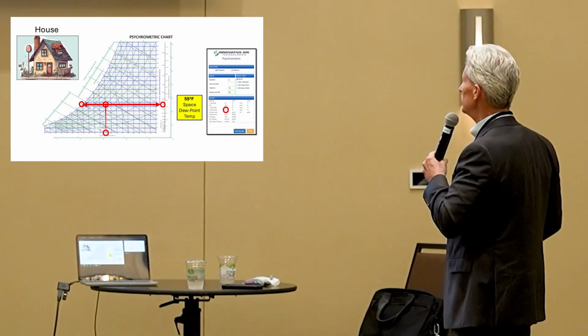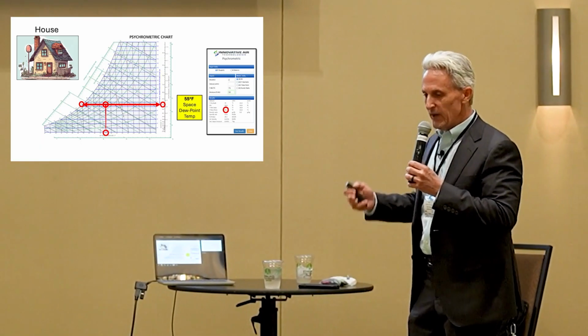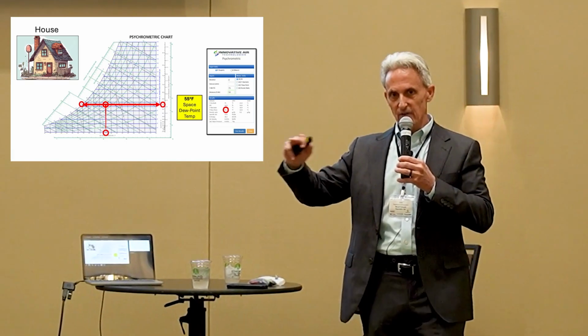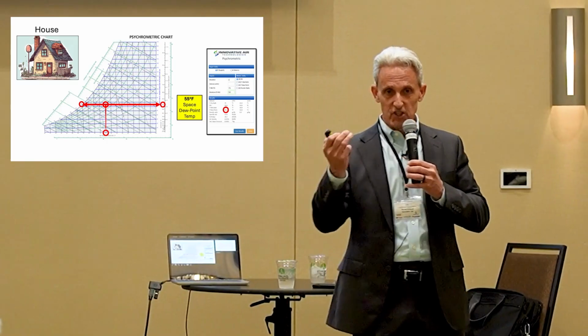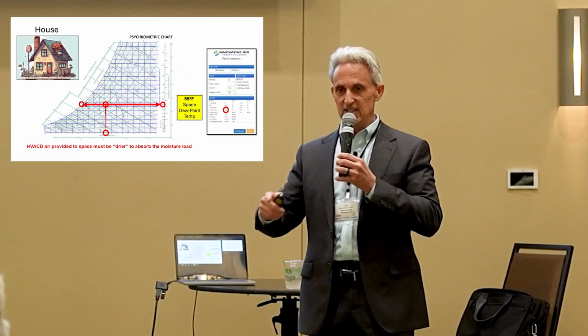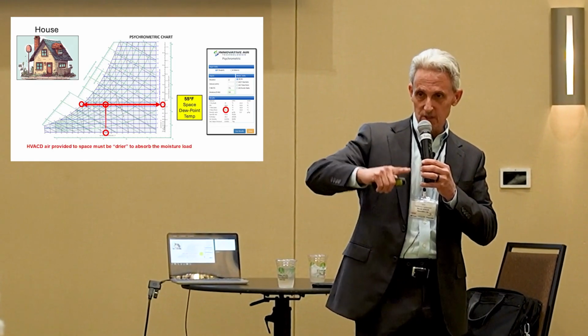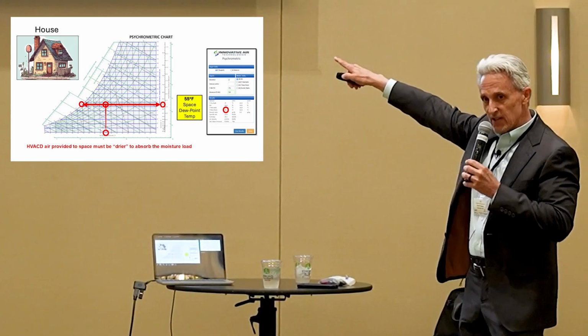All right? Now, I'm going to tell you right now, and I'm going to say this a couple more times, it is important. We are assessing the dew point temperature in the air, in the environment, and where we want to maintain it. In order to achieve it, the HVAC system has to provide drier air to the space. The dew point temperature of the air coming out of the HVAC system needs to be lower to be able to absorb the moisture load in the space and maintain the space at that dew point temperature.